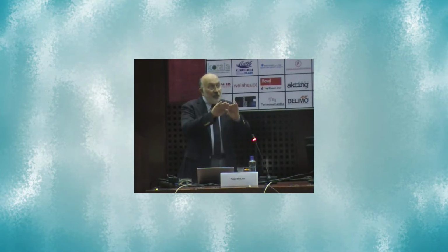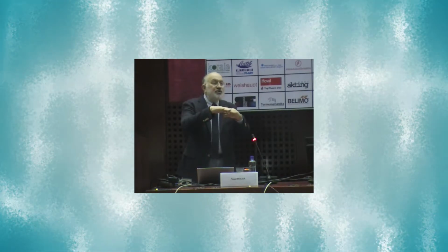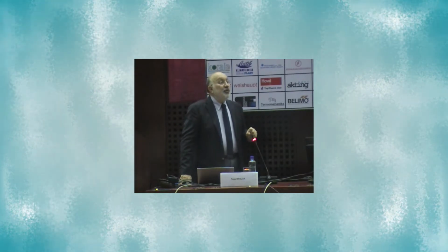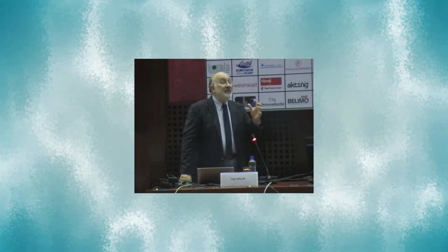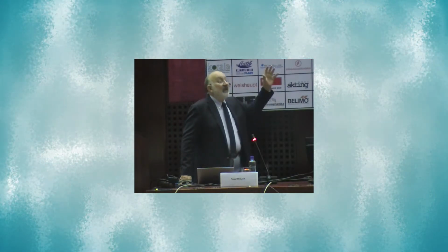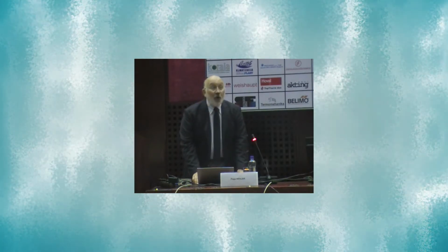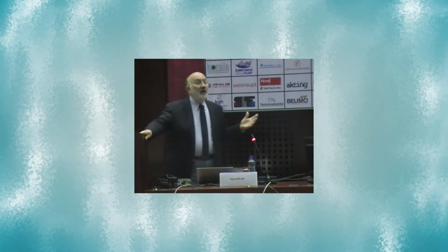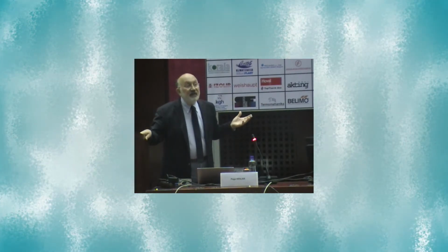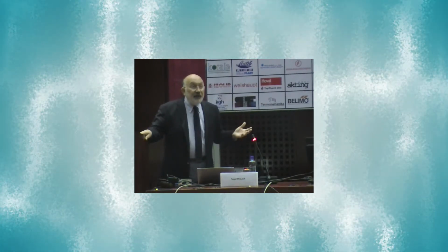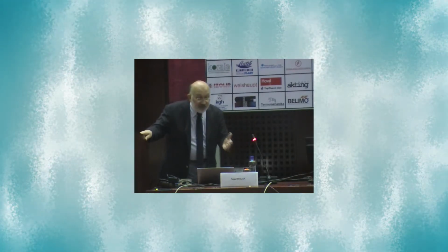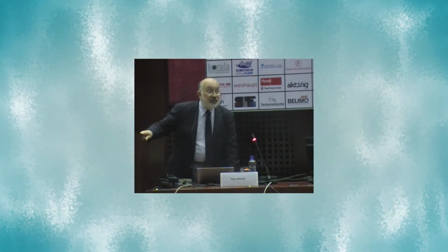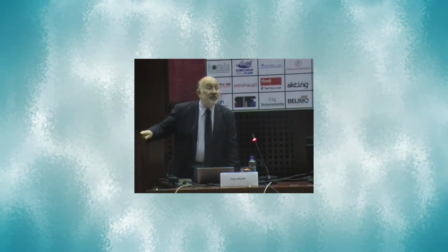diameter. You assume that the top of the fins are kind of pushed into the valley of the lower part, and you create the tube of the same diameter but smooth. Here it is actual smooth tube because they are very, very similar. Okay, with all of this, you see this is maybe the key of the message about the effect of microfin tubes. If you buy that tube, you will have 34% higher heat transfer coefficient, and pressure drop will be 23% higher.